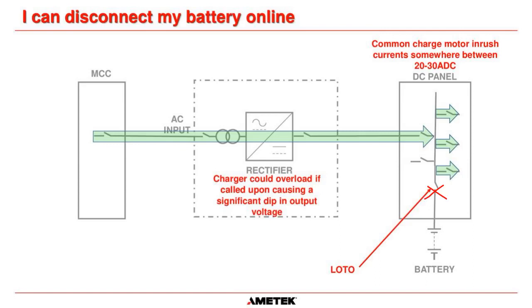So if you had this battery locked out, the charger could overload if called upon, which could cause a significant dip in the output voltage, because what a charger does to protect itself, if it went above 30 amps, the only control we have is to reduce the voltage out of the charger to maintain this 30 amps. And for switchgear systems, the common charge motor inrush current is somewhere between 20 and 30 amps. So let's say two motors for your tripping and closing supplies came on at the same time. That means you're going to see 40 to 60 amps. Okay, it's just going to be for a short period of time, but when you do that, the output voltage of the charger could go down to maybe 100 volts. And that could affect all the other loads that are connected to this DC panel and could cause them to drop out. So that is not a good situation.